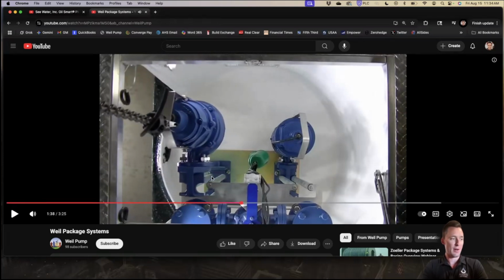Yeah, so nice look down at how that all looks installed. It becomes really important to have a large cover up top so you can clear this opening. So a lot of our minimum basin sizes, minimum cover sizes, minimum openings in the cover get a little bit bigger with these rail systems, because now you have a pump with a sliding bracket that needs to clear out through the cover.